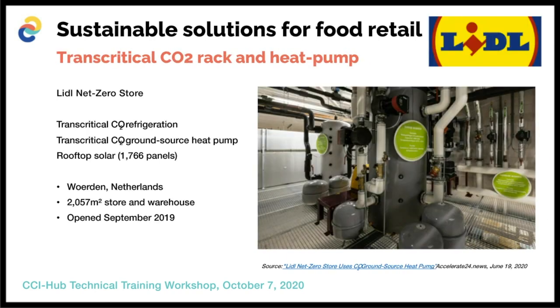Transcritical rack combined with the heat pump. This is a Lidl net zero store concept that has a ground source heat pump, which provides the condensing of the CO2 transcritical throughout the year, hence improving the energy efficiency. So this store was opened in September 2019.